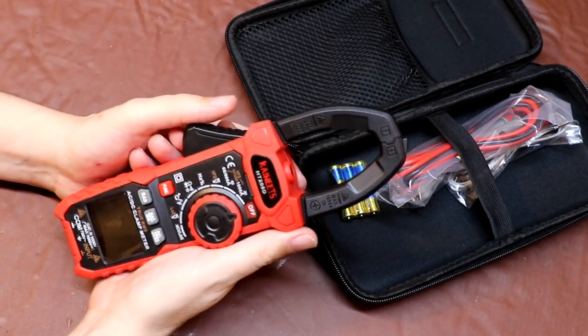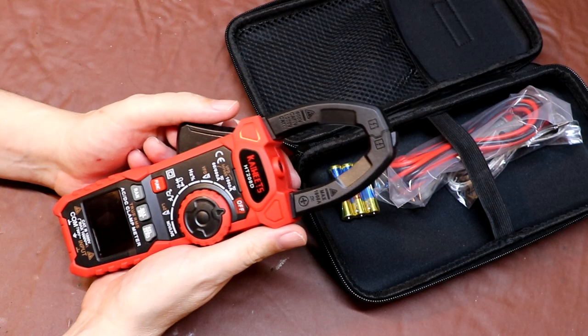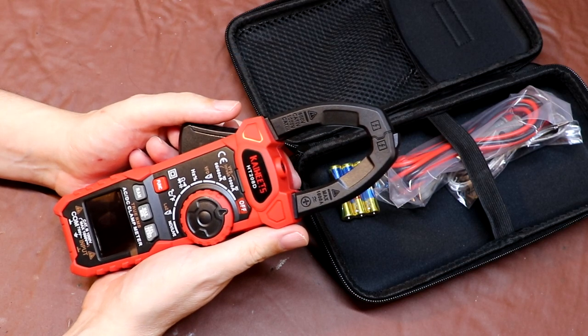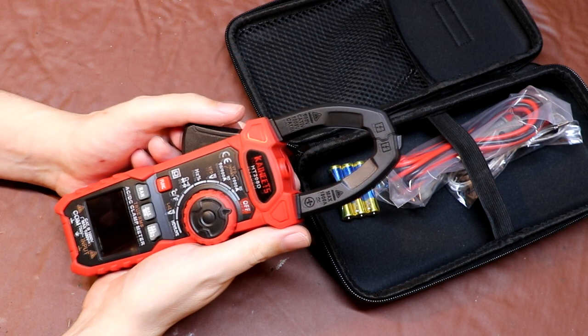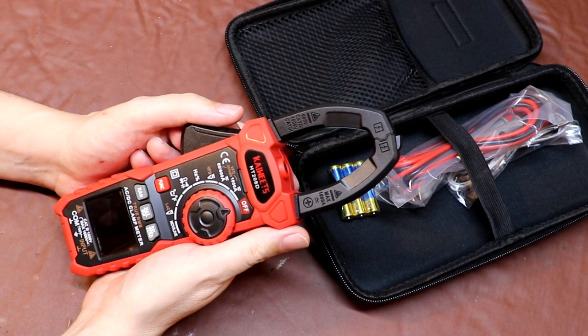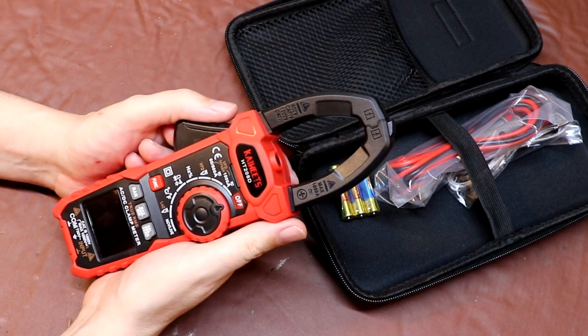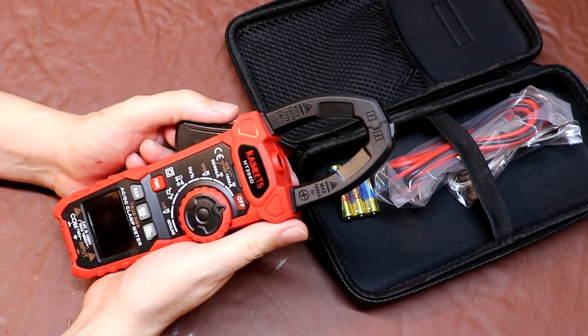Now this is what they call a clamp meter, and the idea behind a clamp meter is that you can make non-contact current measurements. So of course you'll know that when you use a traditional amp meter, you have to cut into the circuit and put the meter in series with the current carrying conductor. So the main feature of this type of meter is the fact we don't have to cut into the circuit to make a current measurement.